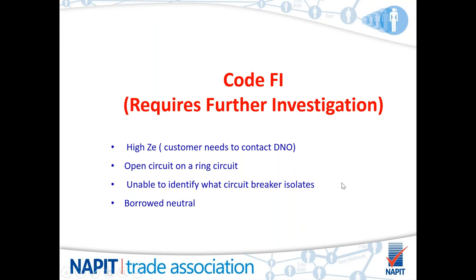An open ring circuit on one of the conductors, you know there's a problem. It is sometimes hard to track down, and would require further investigation to do that. Unable to identify circuit breakers that isolate certain pieces of equipment, you can spend time switching things off, and if you can't see anything going dead and the customer's not aware of anything going off, then again, further investigation to find out where the cable actually is terminated. Borrowed neutrals can also be classified as further investigation. Depends on how they run, depends on what problems it would give you.